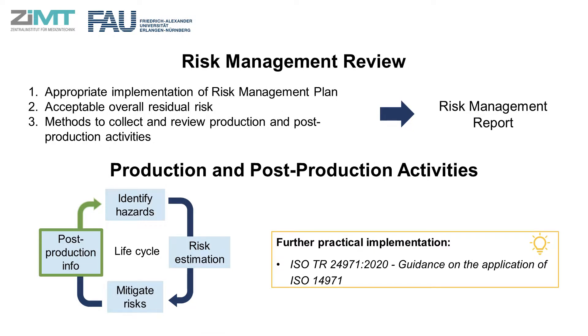As mentioned at the beginning of this video, risk management is a cyclical framework where post-production activities feed back into the risk analysis. After the completion of the initial risk management process, manufacturers need to continually and actively collect and review information in the production and post-production phases. The post-production information provides an opportunity to continuously improve risk management, in turn reducing the potential risk. Further understanding of how to implement ISO 14971 for your medical device can be found in the technical document ISO TR 24971:2020, Guidance on the Application of ISO 14971.